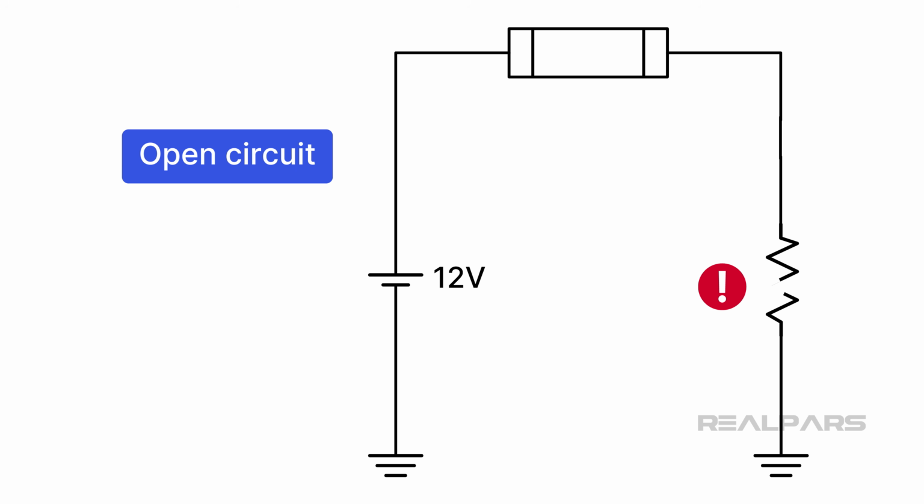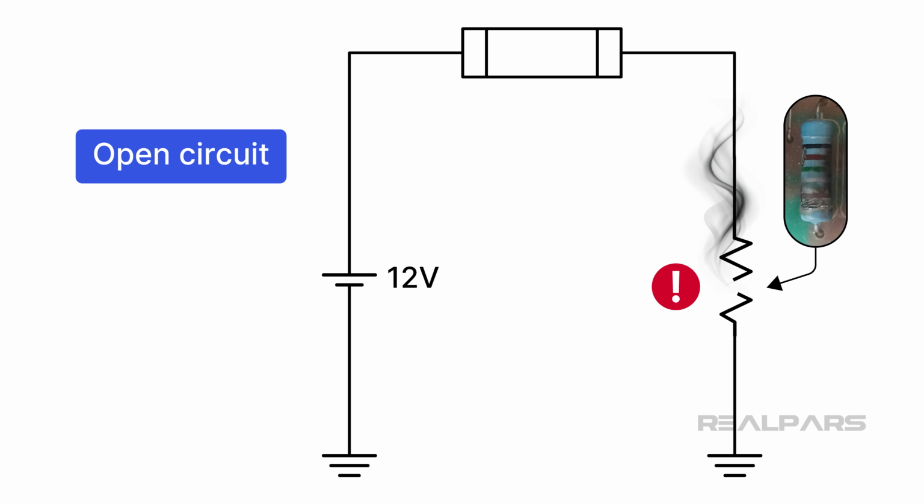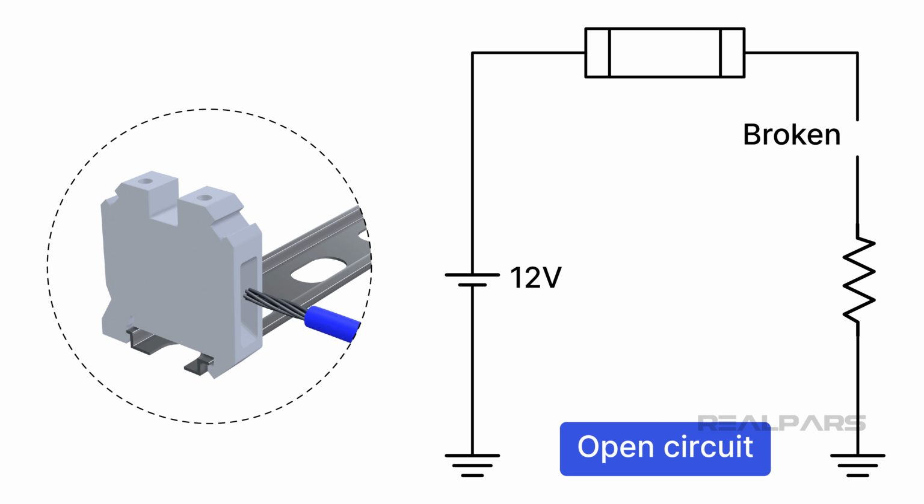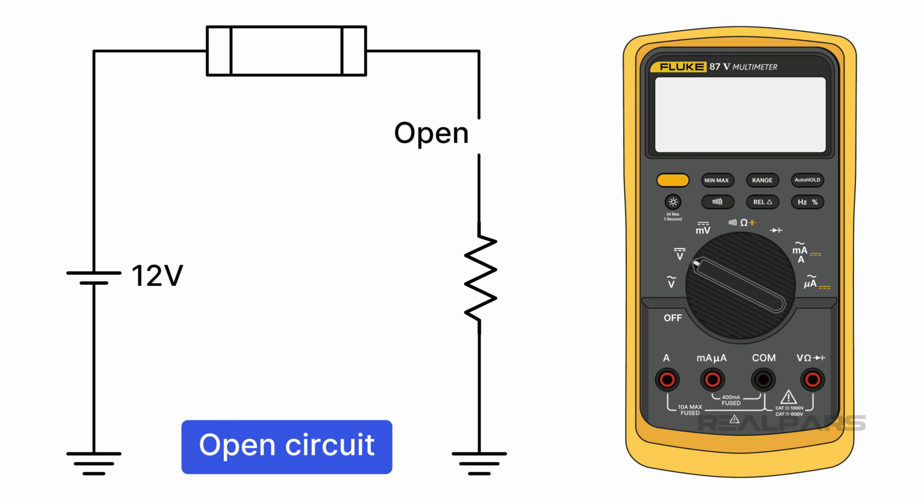An eagle eye and nose will often detect burnt components by their appearance and smell. Other culprits include broken conductors and loose terminals. Open circuits are best found with a voltmeter in an energized circuit, and we will show you how.